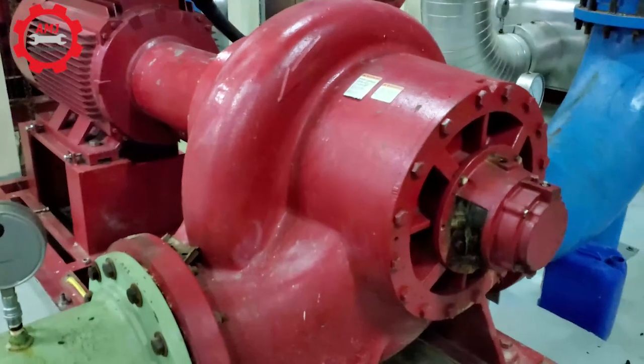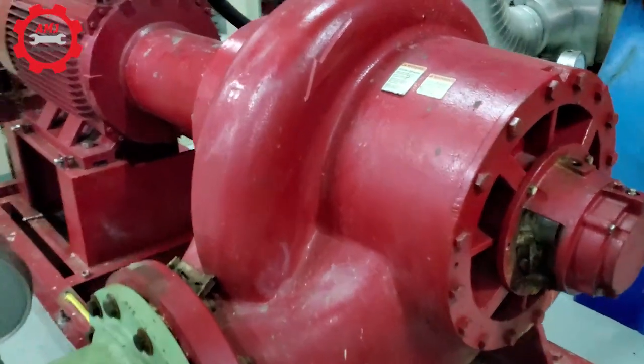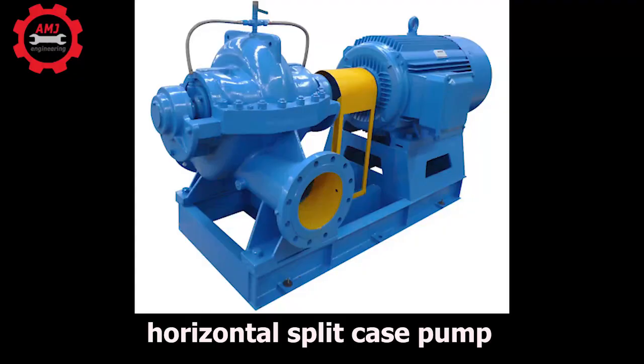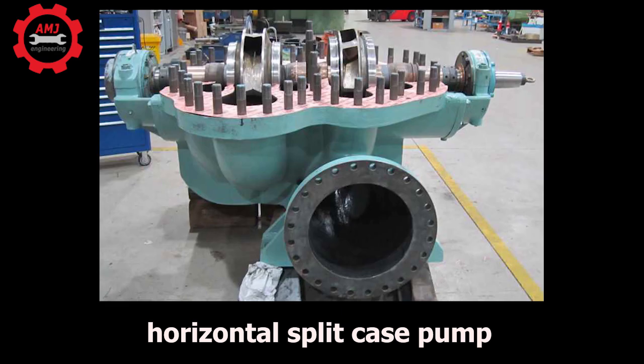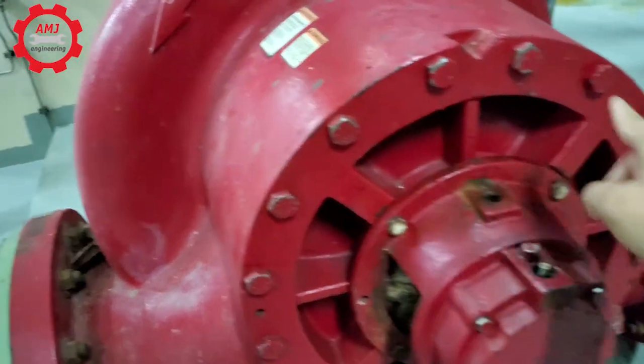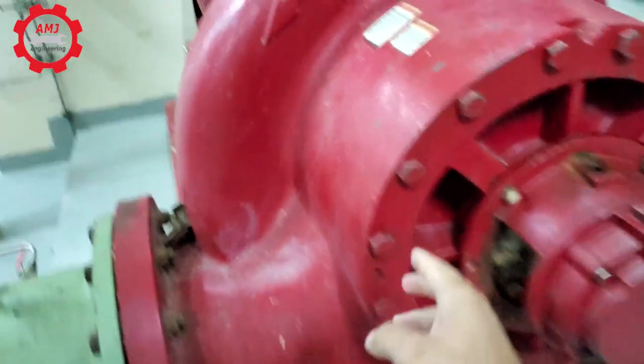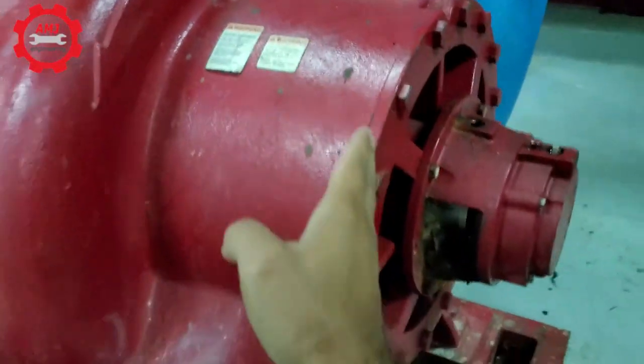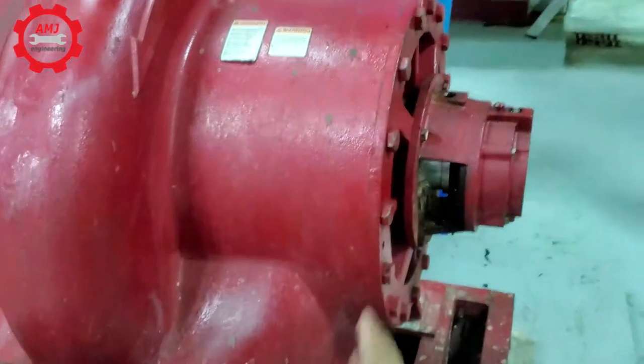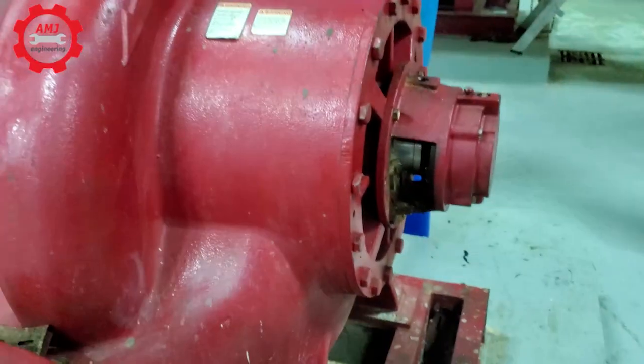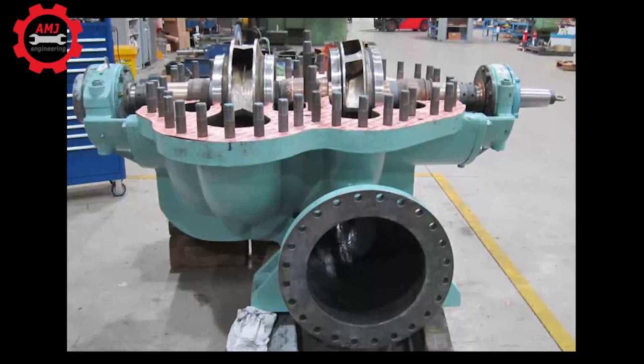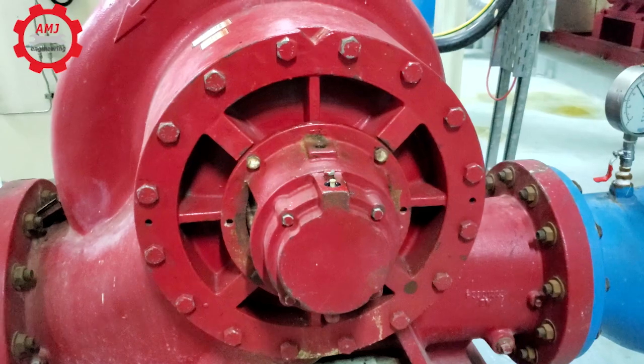Split case pumps are available as horizontal or vertical split case. For horizontal split case pumps, the impeller casing is usually split in the horizontal plane. For vertical split case pumps, the impeller casing is split in the vertical plane. Having the casing split is an added value to the pump because it allows full access to the impeller for maintenance.